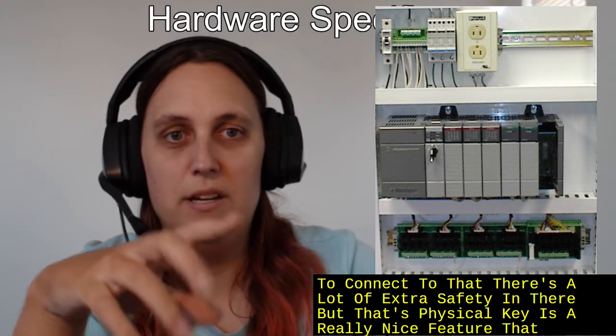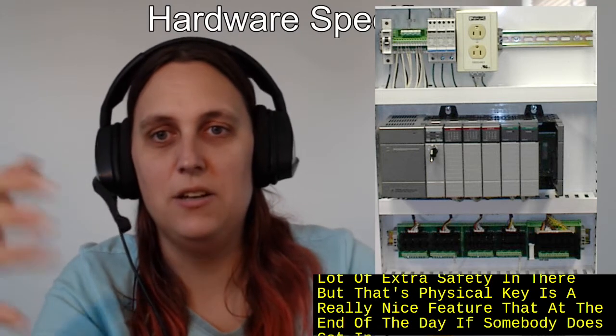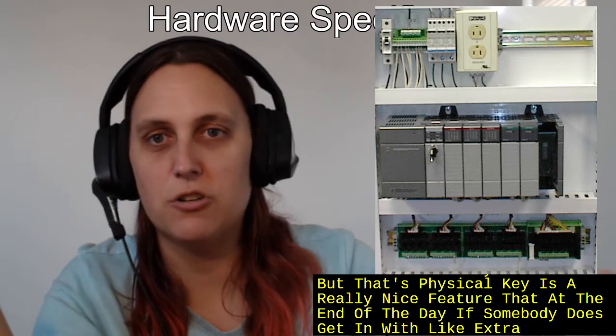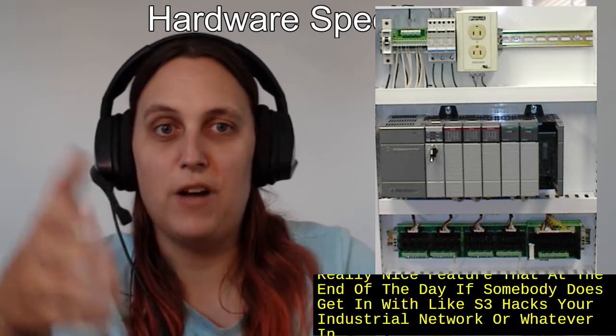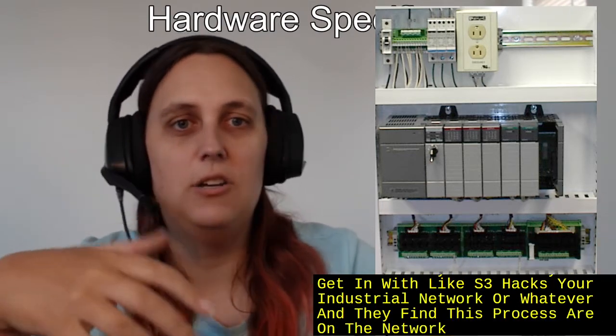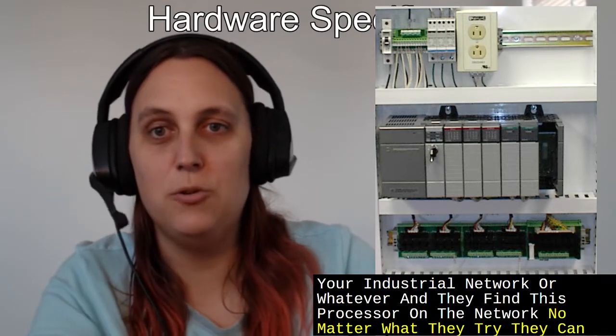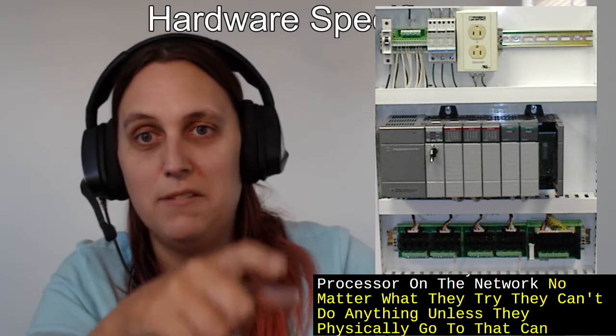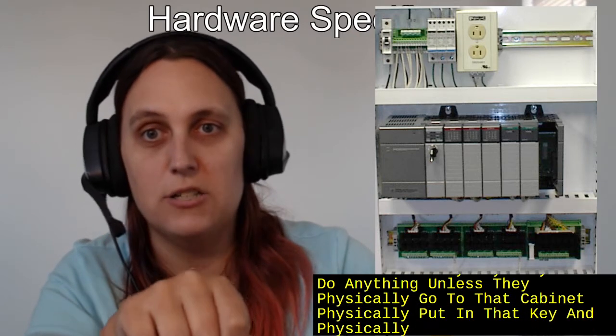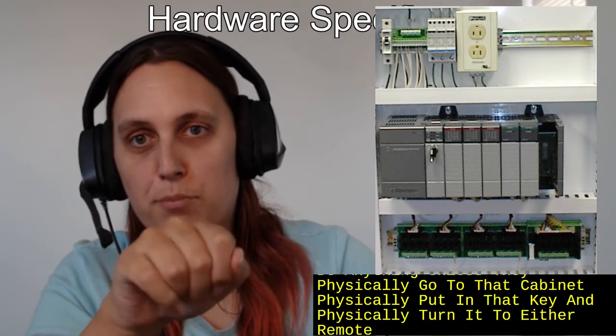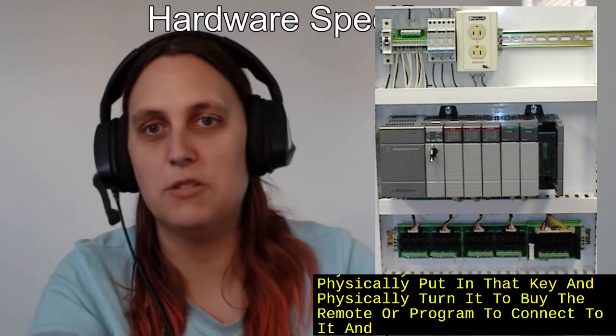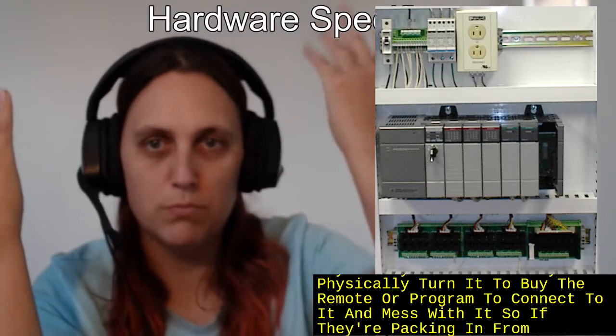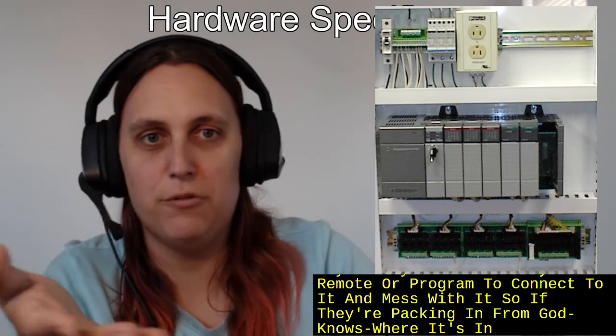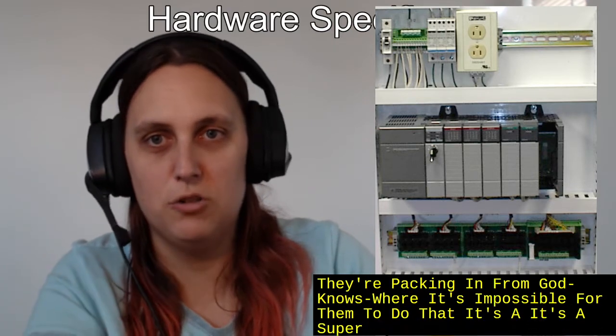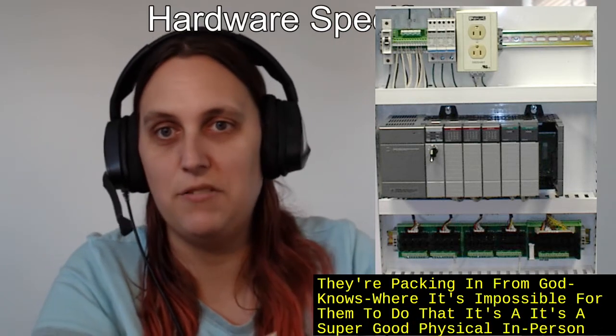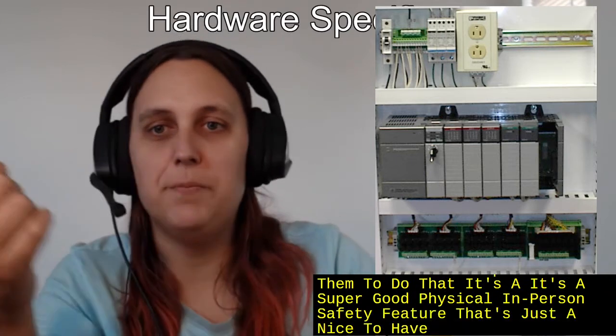At the end of the day, if somebody hacks your industrial network and they find this processor on the network, no matter what they try, they can't do anything unless they physically go to that cabinet, physically put in that key, and physically turn it to either remote or program to connect to it and mess with it. So if they're hacking in from, God knows where, it's impossible for them to do that. It's a super good physical in-person safety feature that's just nice to have.